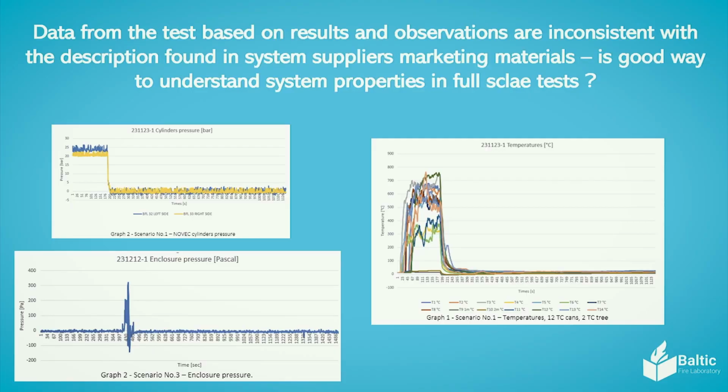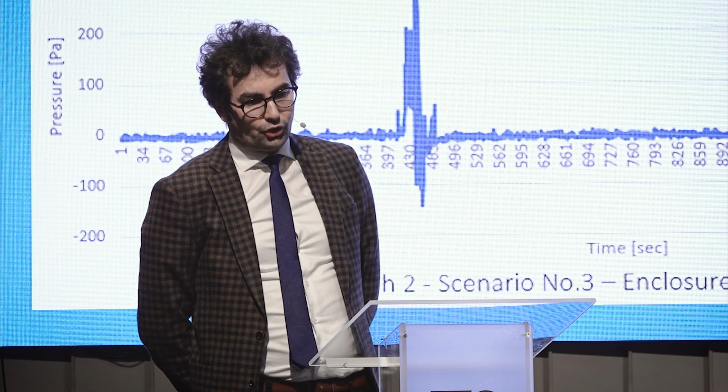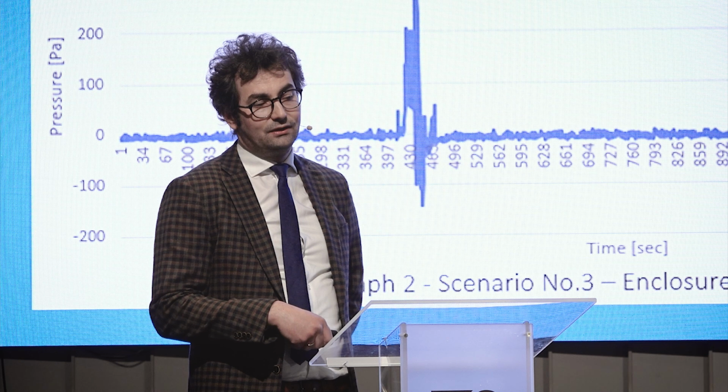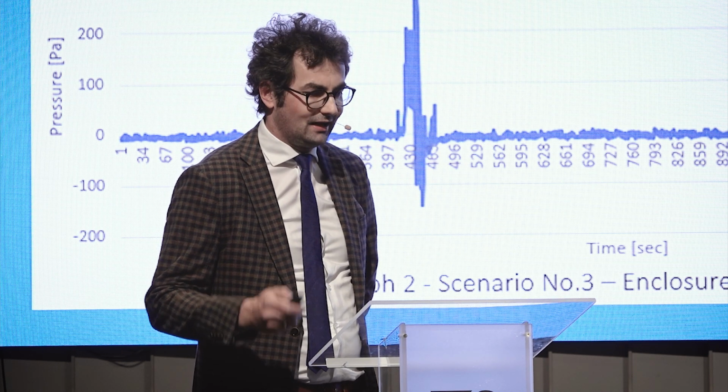What we found is that the data sheets do not exactly tell what was happening during our tests. There is the overpressure, there is a kind of thermal shock in this test as well, and the marketing materials we had were not exactly the same as what we tested, based on the results.